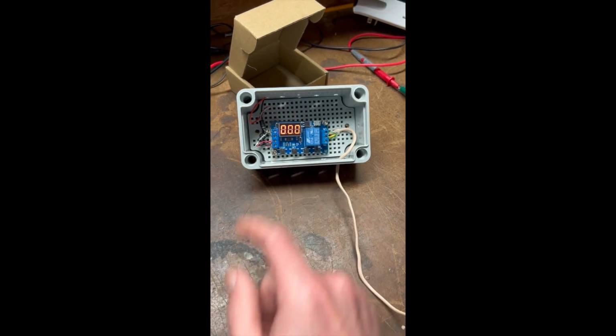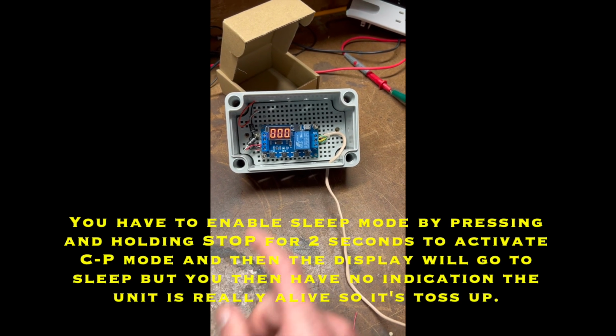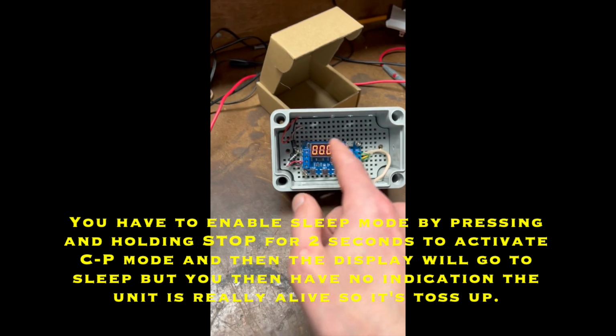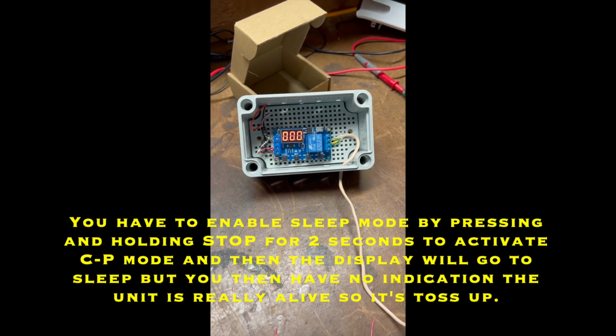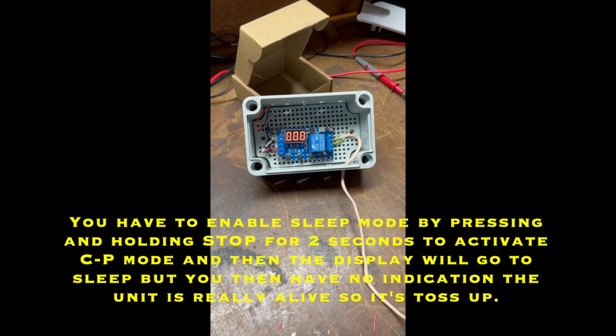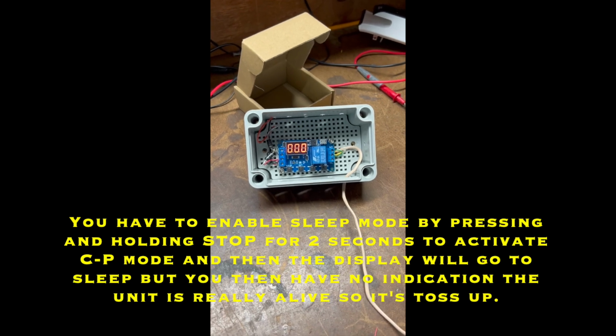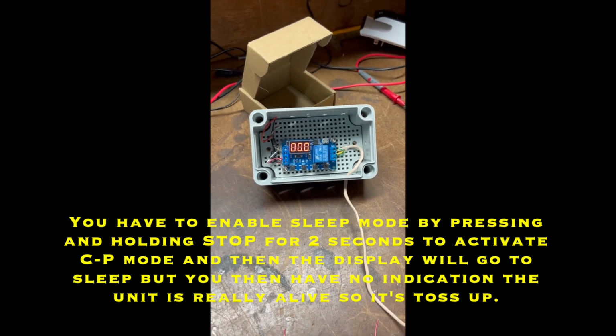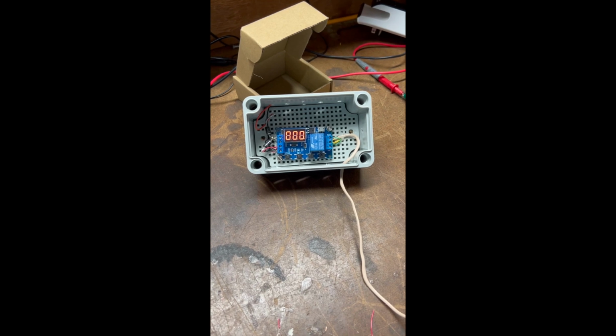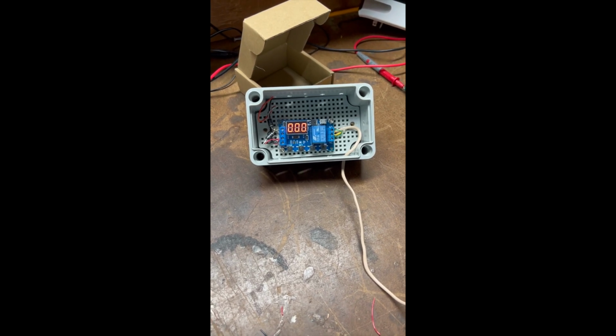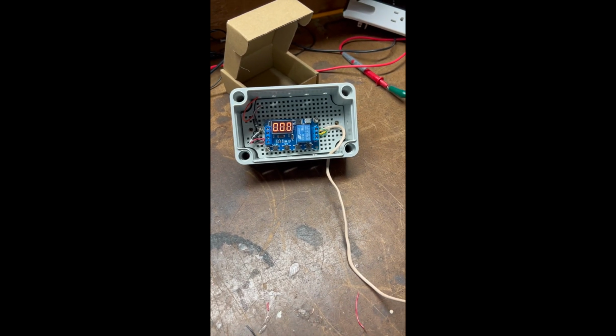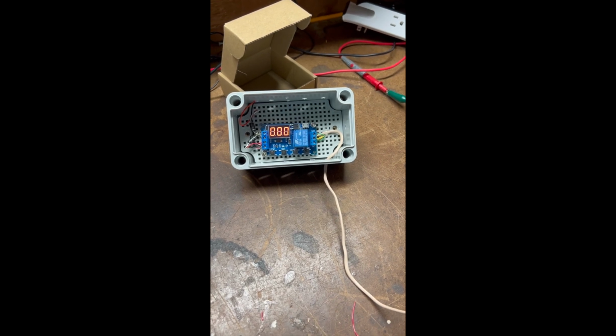Now the manual does say that after 5 minutes of the relay not being energized, this display will turn off. I haven't seen that happen yet. It hasn't been that long. In that case, I should be drawing even less than 30 milliamps of power. And you may remember in my previous setup, the relay was always energized, so that display would never go off. The relay was only de-energized in an alarm condition.